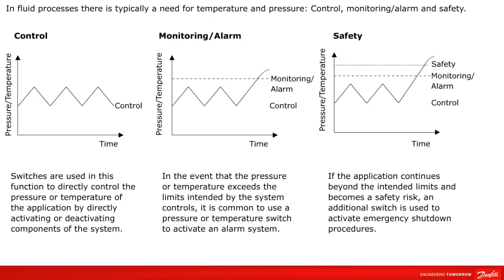In most fluid processes, temperature and pressure switches provide three main functions: control, monitoring, and safety. The control function is shown by the graph on the left. Switches are used in this function to directly control the pressure or temperature of the application by directly activating or deactivating components of the system. In the event that the pressure or temperature exceeds the limits intended by the system controls, it is common to use a pressure or temperature switch to activate an alarm system, shown by the graph in the center. If the application continues beyond the intended limits and becomes a safety risk, an additional switch is used to activate emergency shutdown procedures.